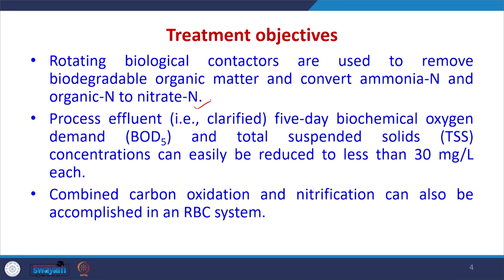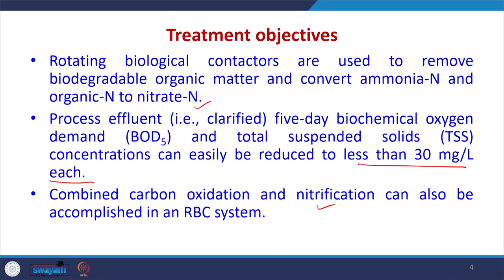Rotating biological contactors have treatment objectives. They are used to remove biodegradable organic matter and convert ammoniacal nitrogen and organic nitrogen to nitrate nitrogen. The process effluent — clarified 5-day BOD and total suspended solids concentration — can easily be reduced to less than 30 milligram per liter each using RBCs. Combined carbon oxidation and nitrification can also be accomplished in the RBC system.